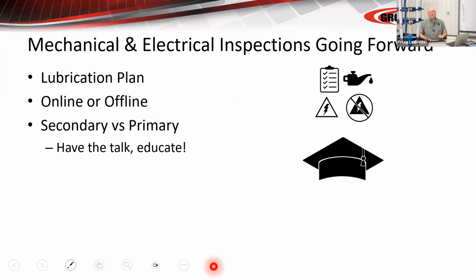So going forward with your mechanical and electrical inspection plan, make sure you have a clean, solid plan for lubrication. Make sure you realize who's going to be doing the lubricants, what you're going to use. There's all kinds of ideas, all kinds of studies. I can do an entire hour, I can do an entire day just on lubricants. But let's just leave it at this. If you don't know what's in the circuit breaker or switchgear at this time, don't replace it with something that might be incompatible. So you have to know what's there, or you have to clean it all out and start from zero, something new. You cannot do that work easily in the field. It's very difficult to properly lubricate a low voltage breaker or a medium voltage breaker in the field. So take all this into consideration. Sometimes you're better off leaving it alone than you are injecting a new lubricant into the situation if you don't know what's already there. And speed and parting times will give you an indication for this, and we're about to get there.